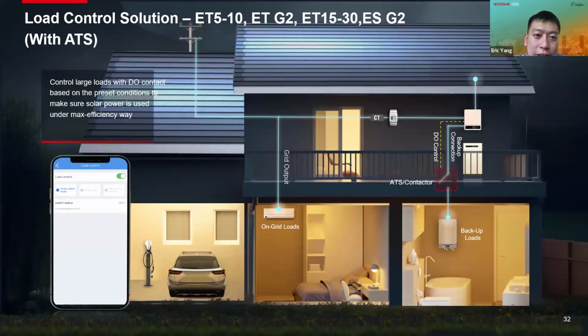Okay, and this is the same port connected to the inverter dry contact. But if the loads do not have the communication port that can communicate with the inverter directly, we can also connect this dry contact port to the contactor, or we can call it the ATS, the switch, and we can control the AC connection of these loads. It means the logic is the same. We can set different values, different PV power, different battery SOC, and different time periods to start, turn on, or turn off these loads.